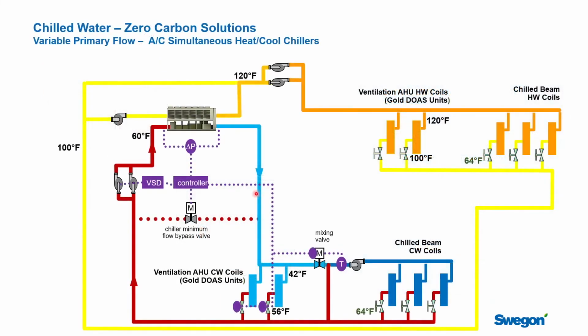Let's look at a system layout with one of these. So here we have an air-cooled chiller, so it's going to be a 4-pipe. From that point of view, we start with the red and the blue. This is our chilled water loop. We're sending water out to these coils at the air handling units in the summer. We can do the dehumidification.